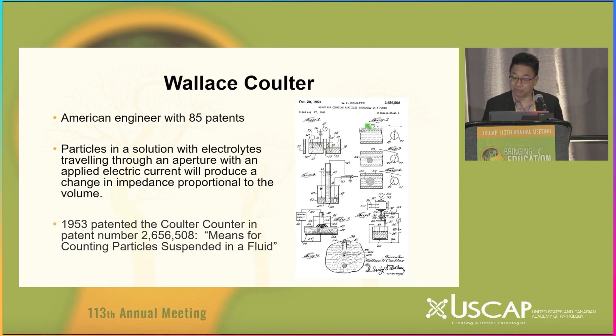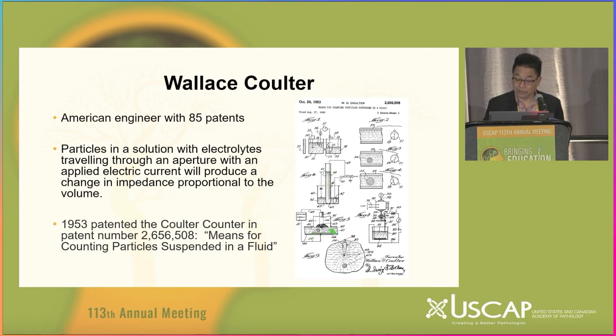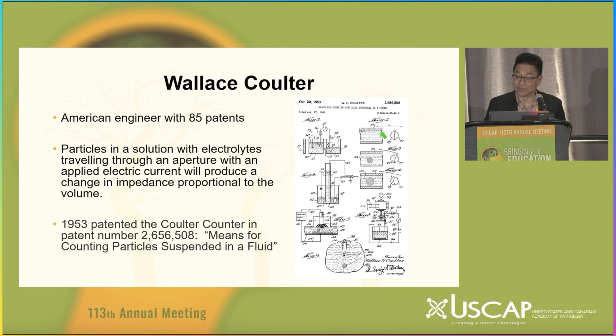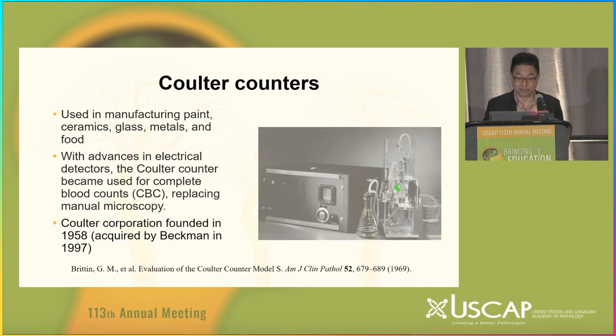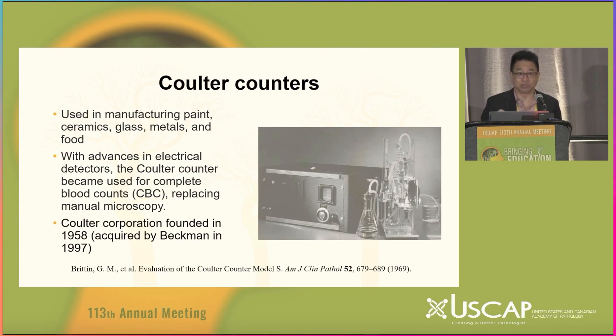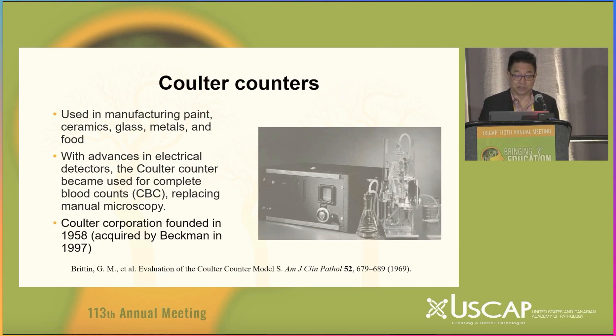This is really interesting. You see the device here where pressure is used to pass things through the orifice. When you look at the orifice on higher power, from this patent submission, in the absence of a particle there's a certain impedance, but when you have a small or large particle, the change in impedance is proportional to the size of the particle. Not only was this the basis for the modern CBC, but it's also used in industries such as paint, ceramics, glass, and materials.